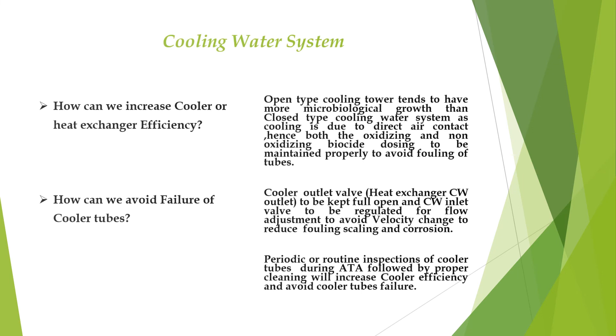How can we increase cooler or heat exchanger efficiency? How can we avoid failure of cooler tubes? Normally, an open type cooling tower tends to have more microbiological growth than a closed type cooling water system, as cooling is done due to direct air contact. Hence, both oxidizing and non-oxidizing biocides to be maintained properly to avoid fouling of tube.